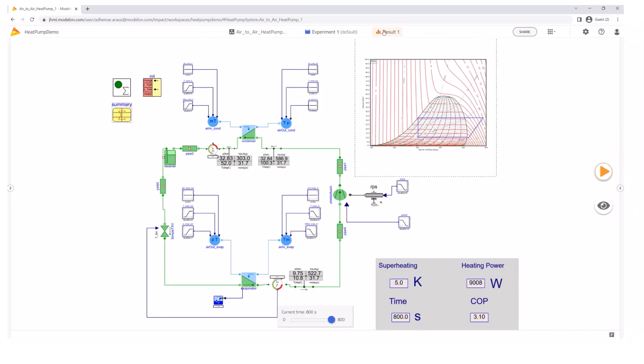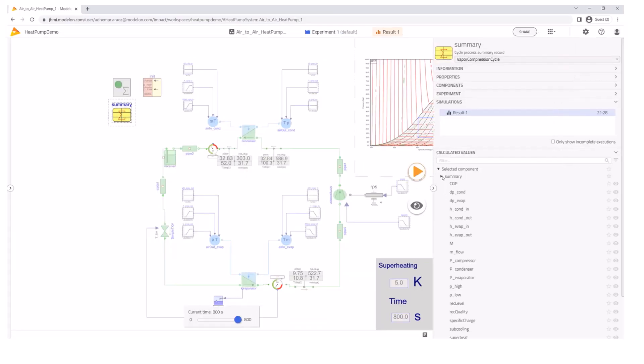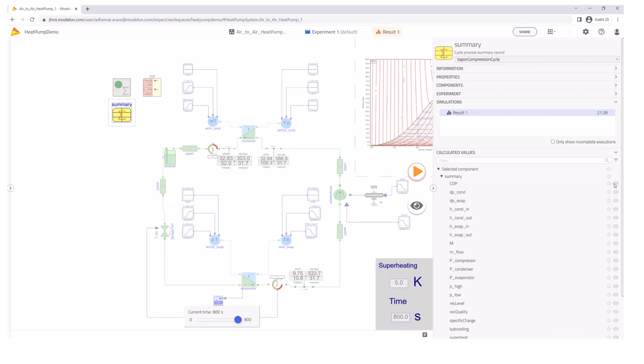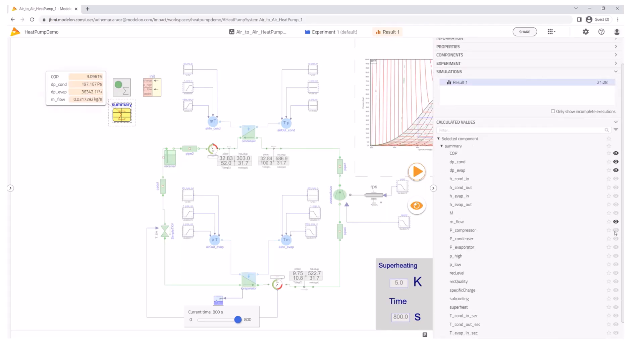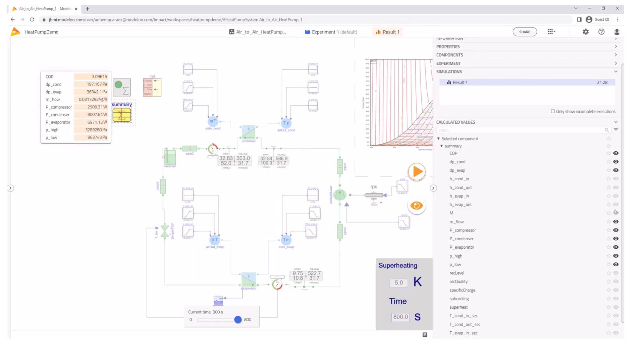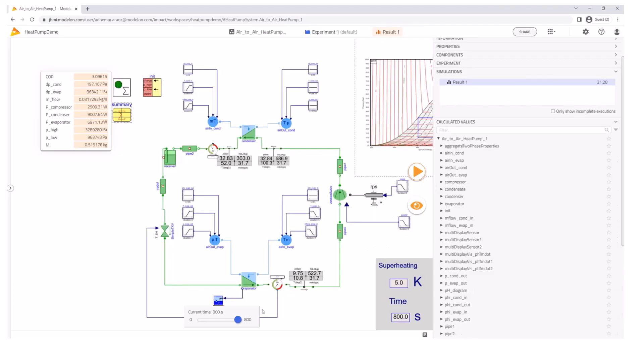I'll run the simulation using the play button. Once the simulation is completed I can explore different results — for example, the COP, the compressor power, the condenser and evaporator power exchange, pressure levels, and the mass of the working fluid.